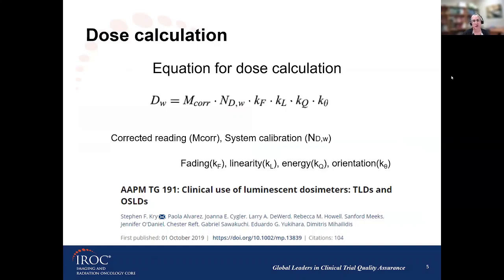The way to run calculation of dose is following Task Group 191. So the equation for dose looks like a TG-51 equation. You're required to look for a corrected reading, have the calibration of the system, which is labeled as N_DW, and then a series of correction factors that are how the commissioning needs to be done. So there's going to be a lot of information in the assumptions you're making on the system and how you define your geometry in order to have these correction factors defined.